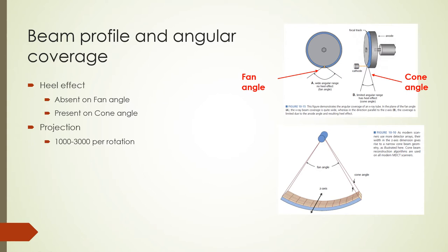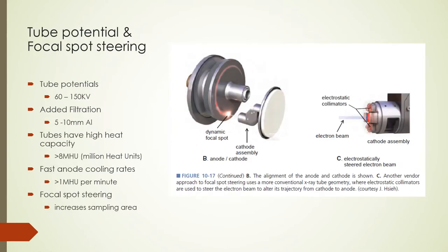There are 1,000 to 3,000 projections acquired per rotation. CT tubes typically operate in the 80 to 140 kV range, but some manufacturers have introduced 60 kV to 150 kV options. 60 kV can be used to reduce dose to smaller patients and 150 kV can be used for increased penetrability of larger patients. The CT beam is heavily filtered with added filtration in the 5 to 10 mm aluminum range, making the beam very hard compared to radiographic beams.